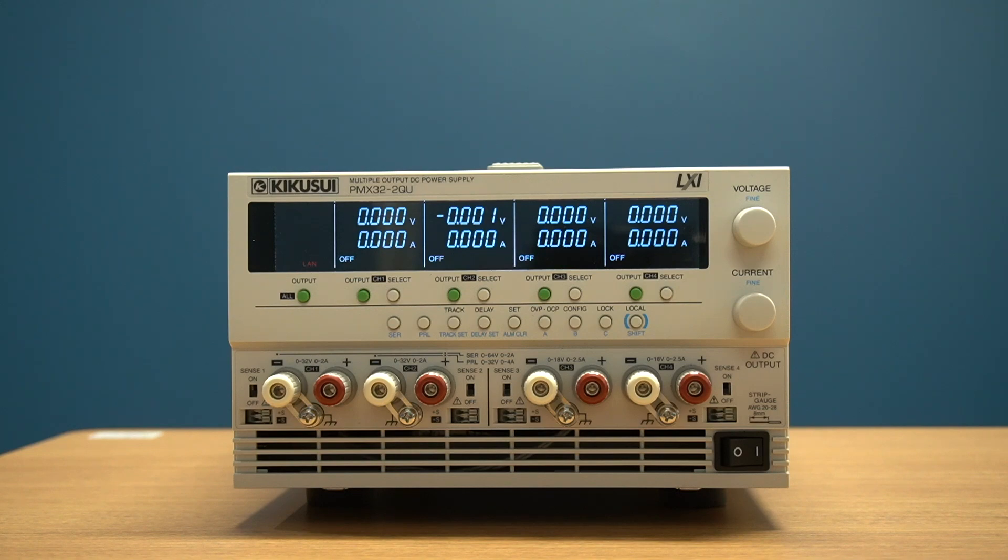The individually isolated channels also allow for increased flexibility in the form of one-touch series and parallel operation. Channels one and two can be connected in series or parallel to double the voltage or current in accordance with your test requirements.